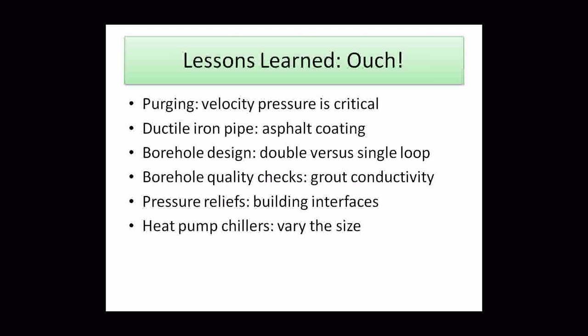Problem is when you get debris in the pipe and you turn it on and get those velocities up, you scarify that. You remove the asphalt, it gets moving into the buildings, and we have to, through our filter systems, constantly change our filters on our strainers. And it's gone today, but it's an issue that you wouldn't have to deal with if you didn't specify asphalt-coated piping. And we use that on our ductile iron for our hot water side.